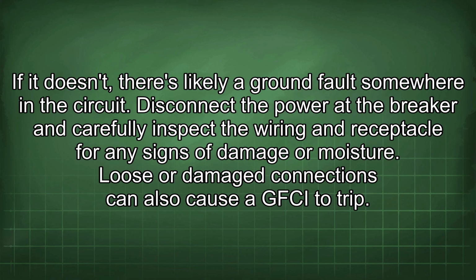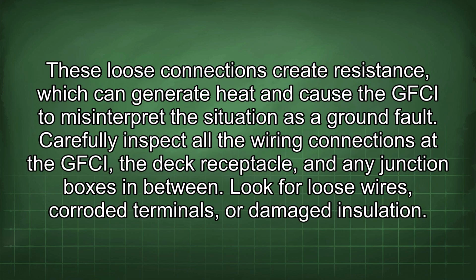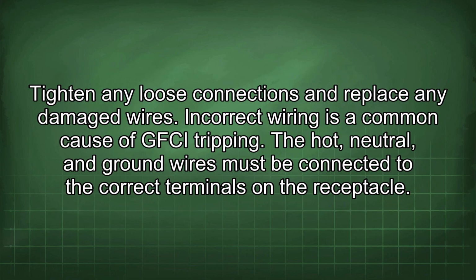Loose or damaged connections can also cause the GFCI to trip. These loose connections create resistance, which can generate heat and cause the GFCI to misinterpret the situation as a ground fault. Carefully inspect all the wiring connections of the GFCI, the deck receptacle, and any junction boxes in between. Look for loose wires, corroded terminals, or damaged insulation. Tighten any loose connections and replace any damaged wires.